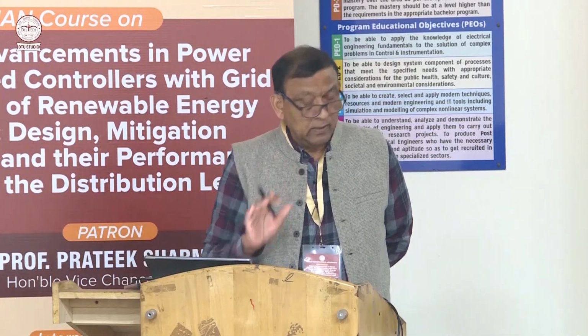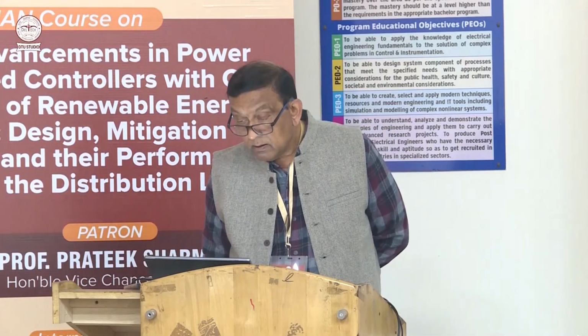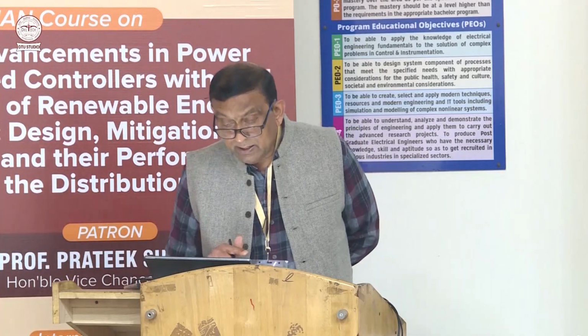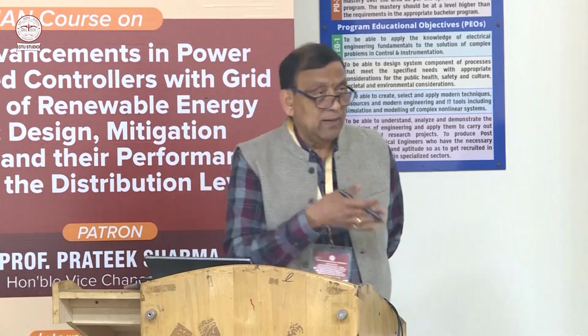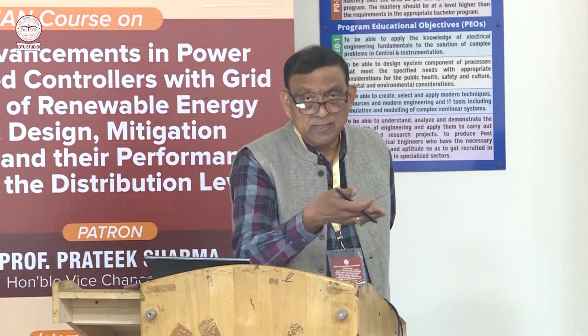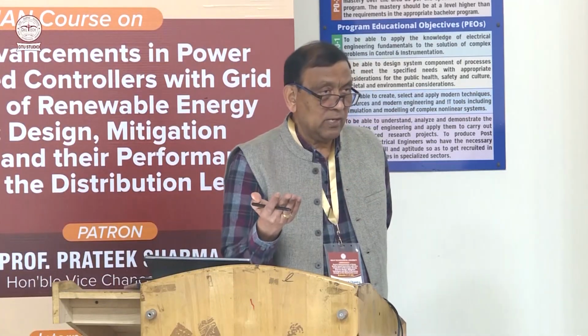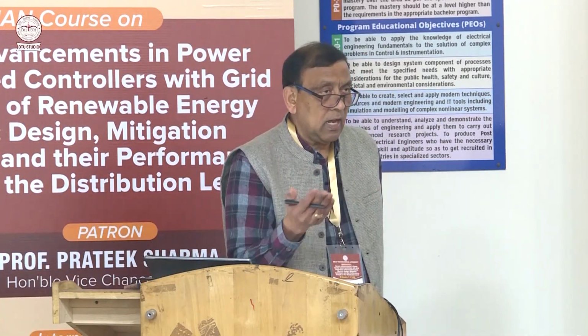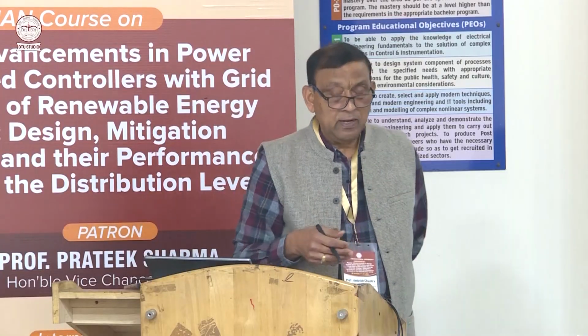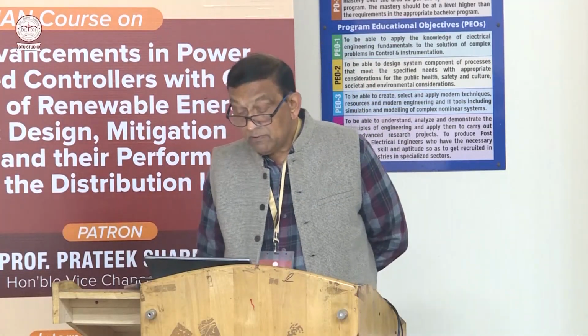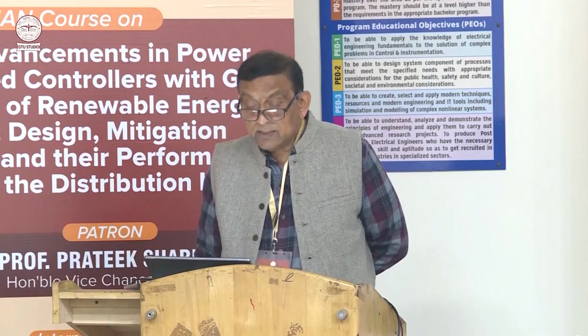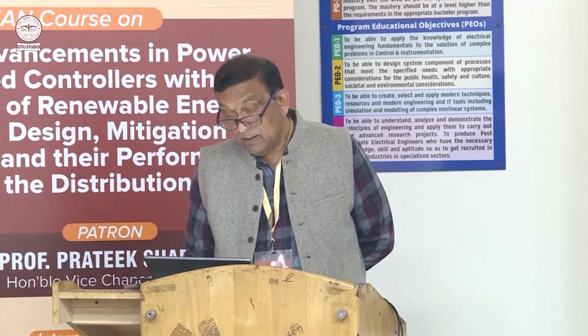limits. Okay, so I will come to that later. TDD also has the same limit, like we always talk about 5% as the THD maximum, but the individual harmonic current limit may be different. So this we will see in the table. So this is the difference between THD and TDD.